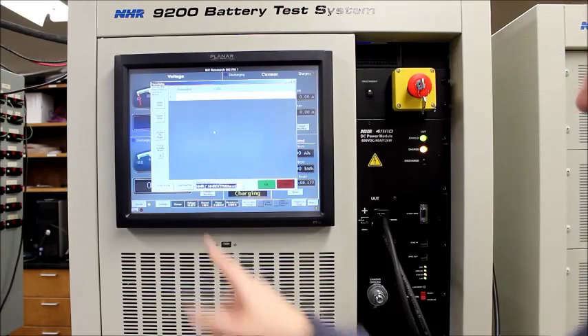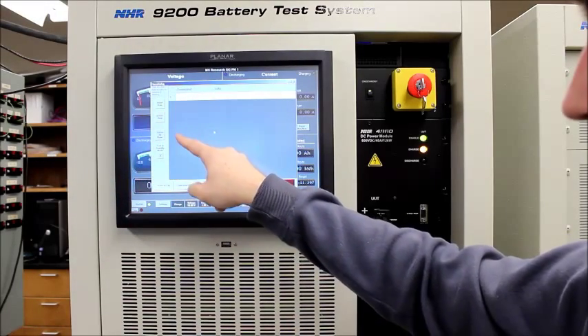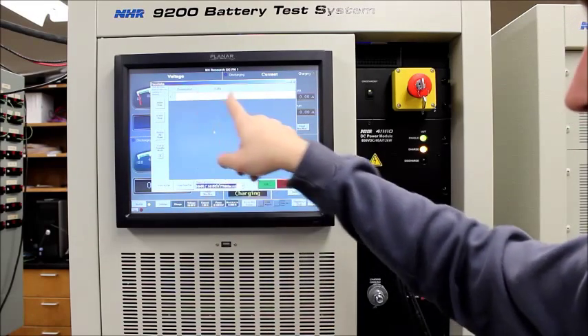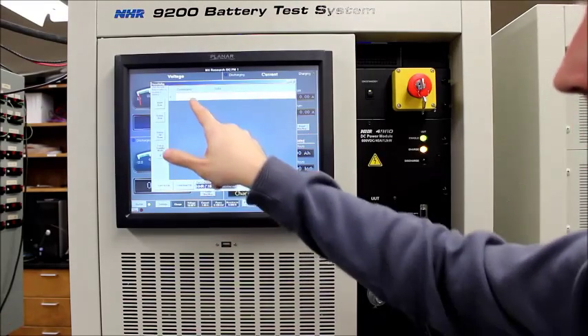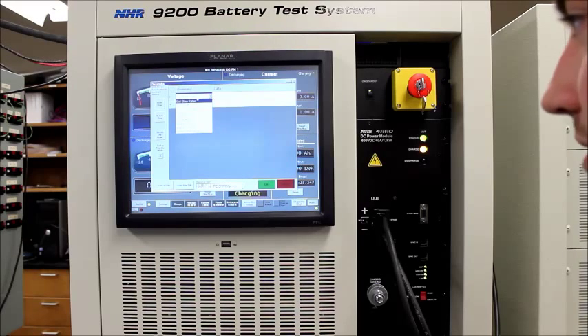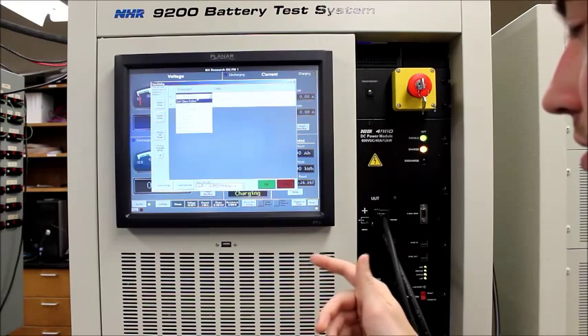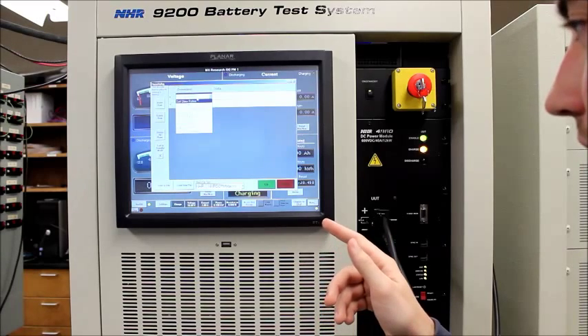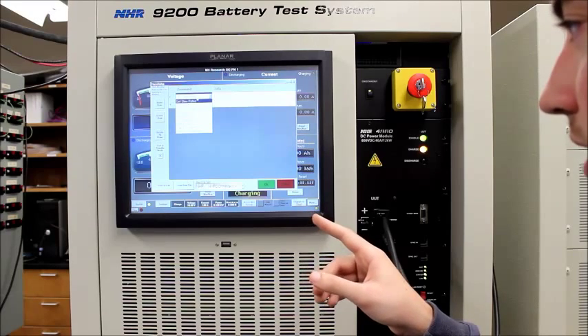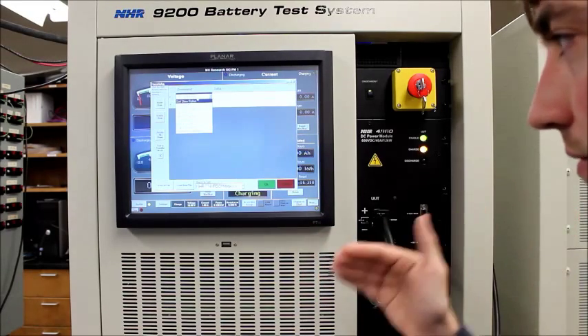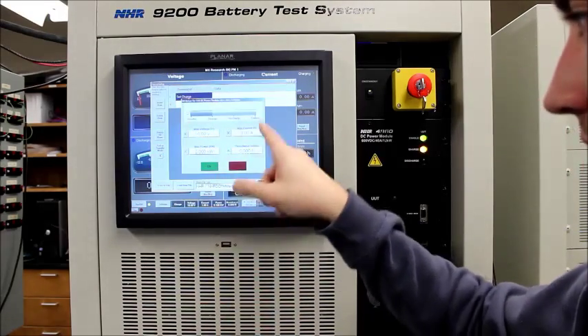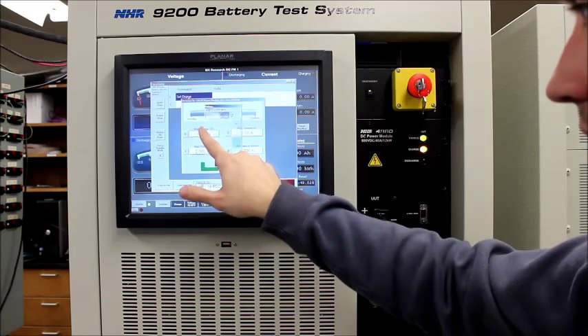Okay, so then you see insert row, delete row, delete all rows, end and standby. And then there's command and data. You click command, you'll see a list: set slew rate, set to off, set to standby, set charge, set discharge, set battery, wait for slew, wait for value, and wait for time delay. So we want to do charge mode at 10 volts. So set charge. And we see the same setting as we had before. So it'll go to this setting during this time.